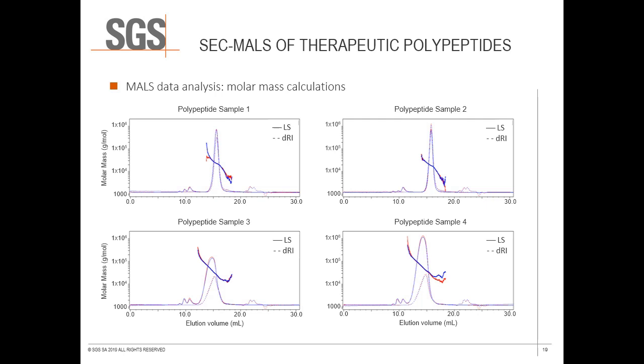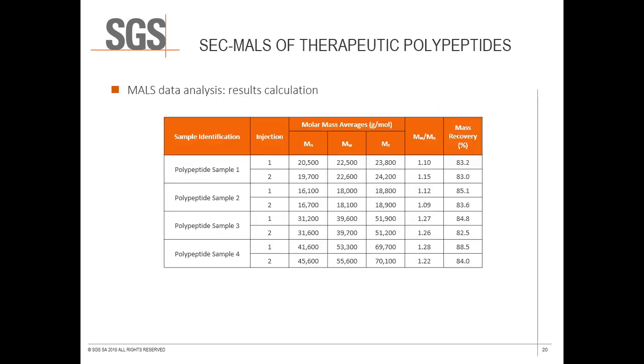As you can see in the presented figures, calculated molar mass values become more erratic and less realistic at the front and tail of the sample peaks. This is due to inadequate signal as the peaks begin and trail off. The effect of this erratic data is minimized by the low calculated concentration of these molar masses, but integration should still be limited to not include excessive amounts of irrational data. This is why integration on the right-hand side of the peak, as shown, does not include the entirety of the refractive index peak tail. This dataset indicates that the polypeptide samples being tested were particularly narrow in molar mass distribution.